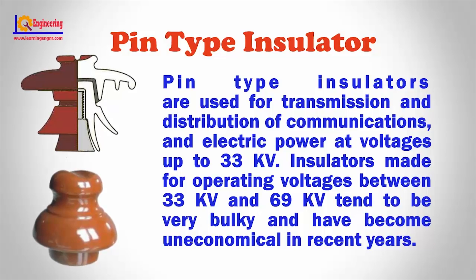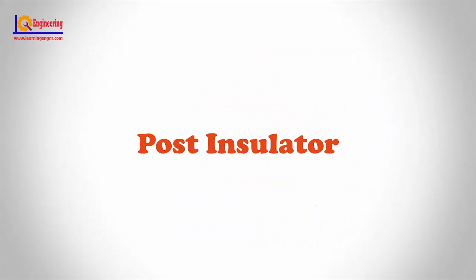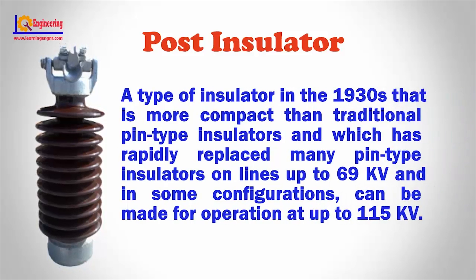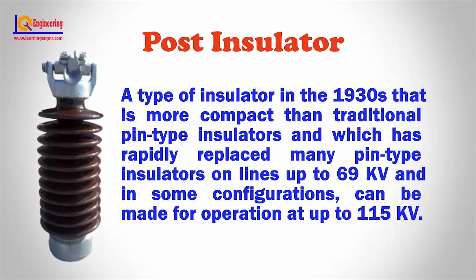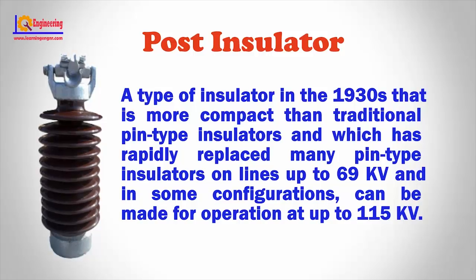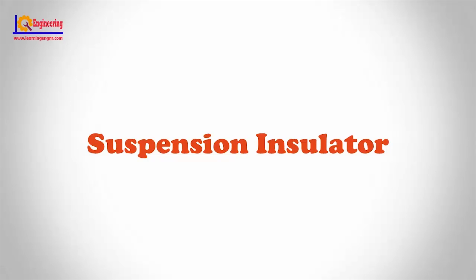Insulators made for operating voltages between 33 kV and 69 kV tend to be very bulky and have become uneconomical in recent years. Post insulator: A type of insulator developed in the 1930s that is more compact than traditional pin type insulators, which has rapidly replaced many pin type insulators on lines up to 69 kV and in some configurations can be made for operation at up to 115 kV.